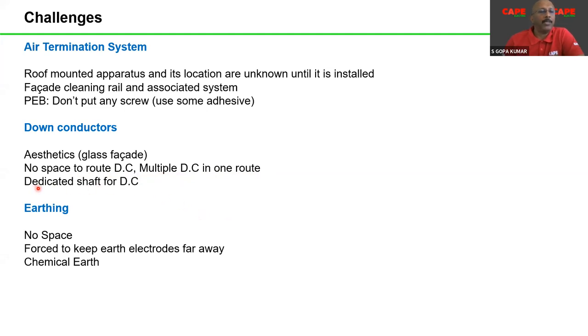And then in some cases, architects are providing a dedicated shaft for the down conductor. So I have three down conductors. You have 15. You require 15 down conductors, and all the 15 down conductors as groups of five, you take through three shafts. That is also not possible. If a typical building requires 10 down conductors, all the 10 must run outside the building, preferably all around the building, as straight as possible. So routing the down conductor through the dedicated shaft is also practically not possible. It is a violation of the standard.